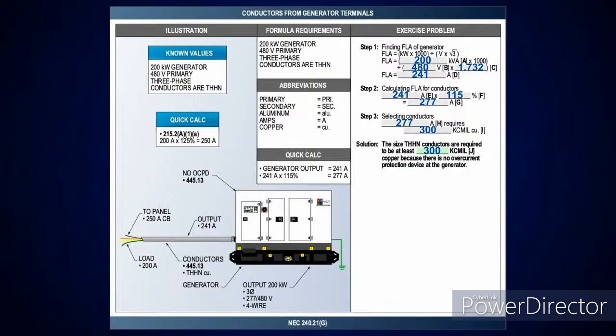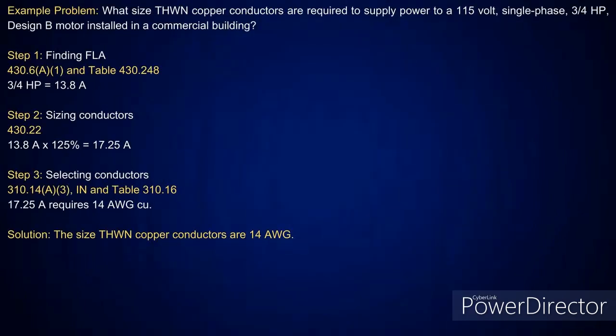And then I'm going to look at sizing this conductors. And the next size up above that is 300 kcmil conductors. Very simple. All of this is easy to follow. You just need to know where you're looking here. Okay. But the one thing I want to point out, when we were doing the secondary side of that transformer, the conductors for it, and then I'm doing it here for a generator, I still did the same calculation to determine what my full load amperage was. Okay. Right. Now, that got us through that.